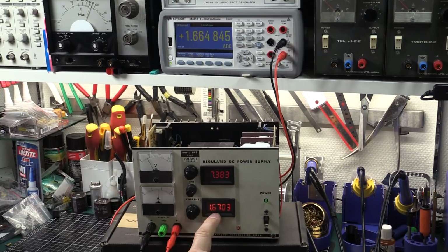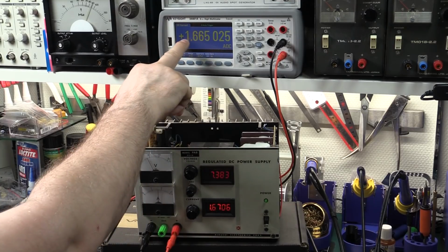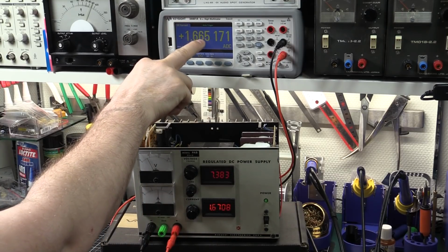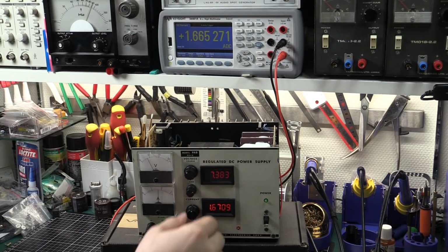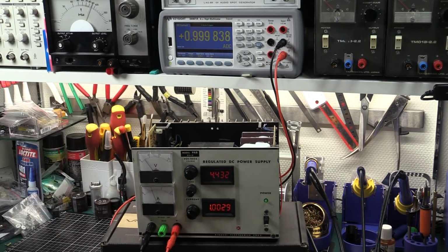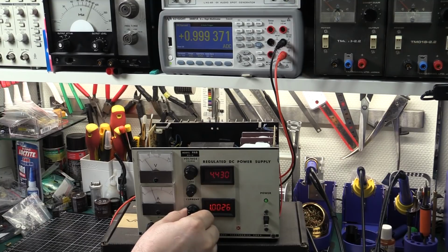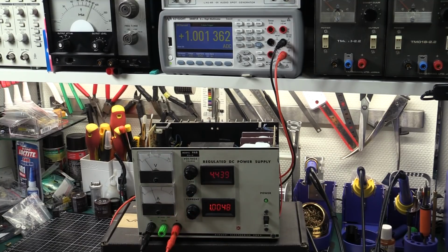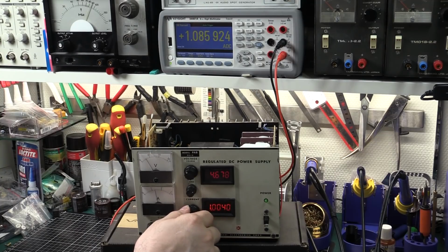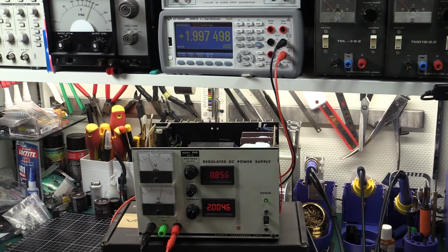At the moment, 1.6704, 1.6, it'll round up to 7, so that's pretty close. Dial that down to about 1 amp, and we're reading basically 1 amp. We're off a tiny bit, but that's pretty close, I'm not going to sneeze at that. The analog gauge there is working as well.